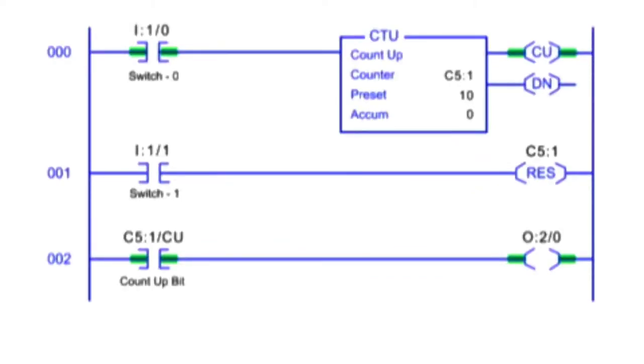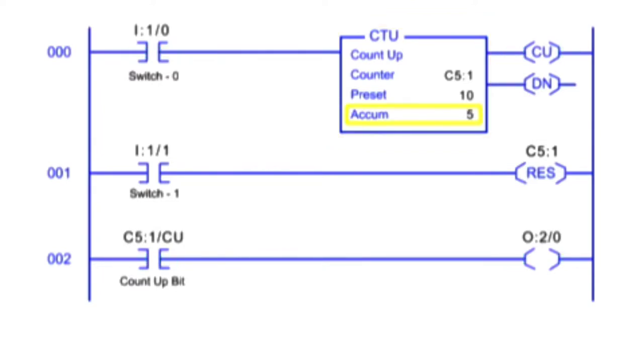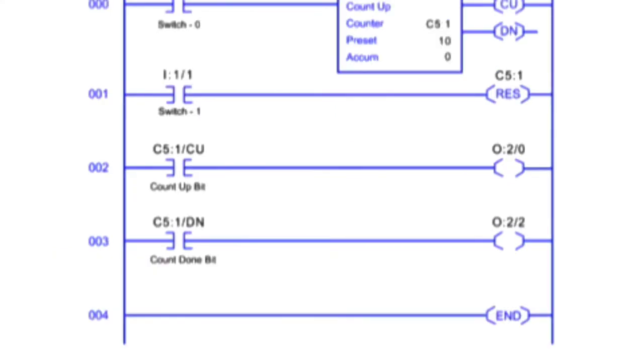Count up and count down instructions are used to count rung transitions. The count up instruction, or CTU, is used to count false to true rung transitions. When rung conditions for a CTU instruction have made a false to true transition, the count up enable bit is energized and the accumulated value is incremented by one count.